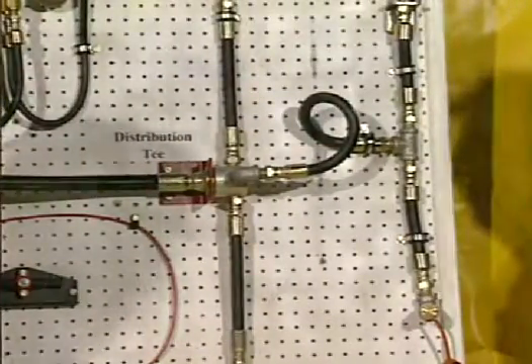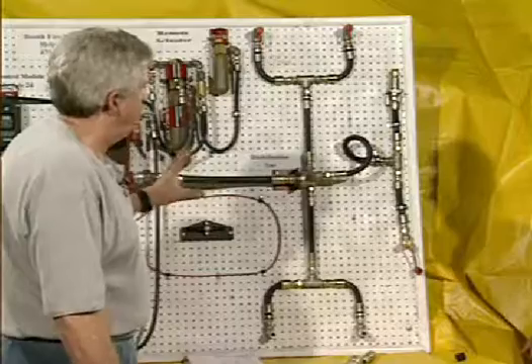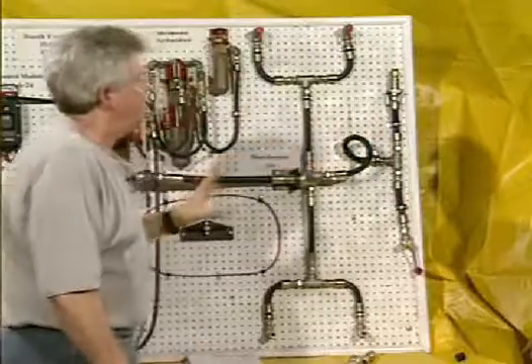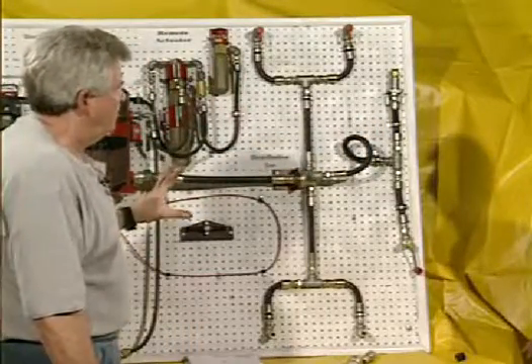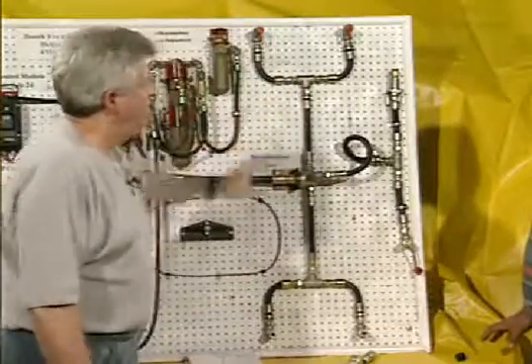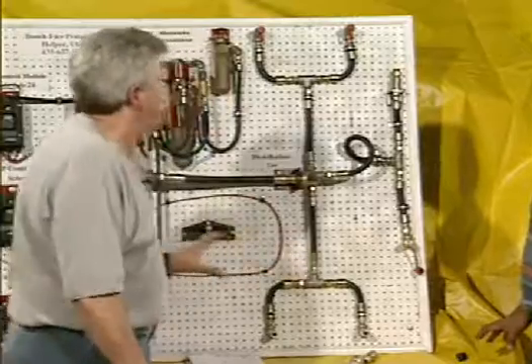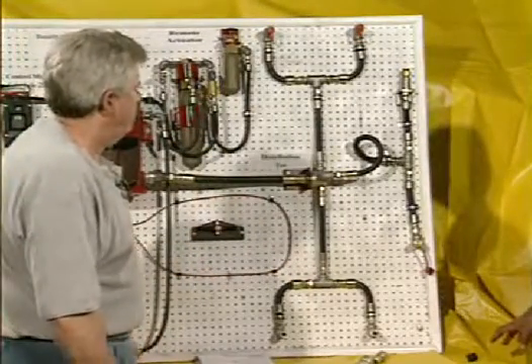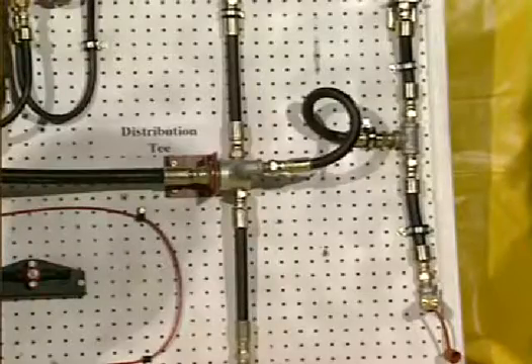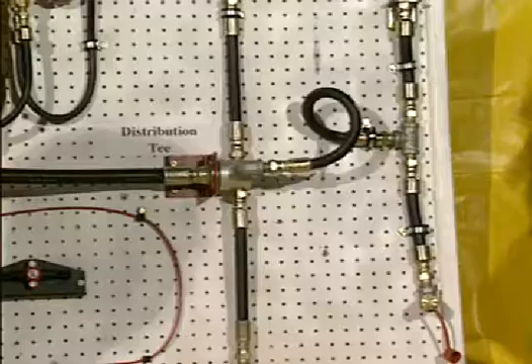That's maximum. As you can see here, the hoses are pretty much the same length here. You don't necessarily have to be that way. This group here and that group there have to be within 3 to 1 of one another. 3 to 1. Now, what's that mean? Okay, what that means is that the total length of these 3 hoses, we're just saying is 3 feet. The furthest one, or the maximum on the next group of hoses, could be only 9 feet. That gives you a 3 to 1 ratio there. Okay. But you have that limitation on these systems, which, if you notice, I put a curl in this particular hose. You can wrap that hose to make up the difference to give you your 3 to 1.